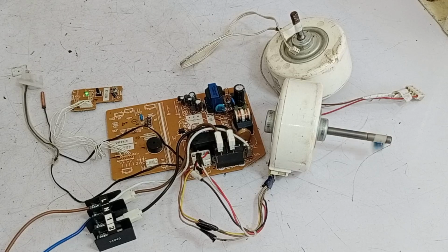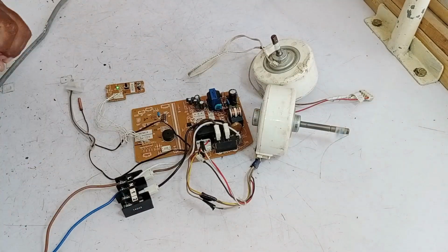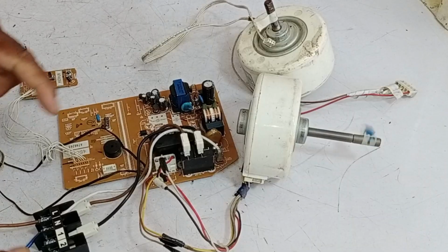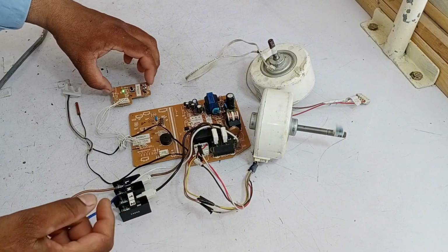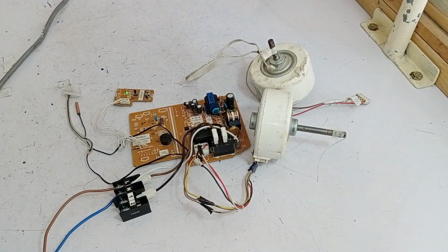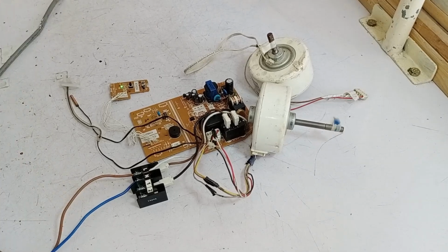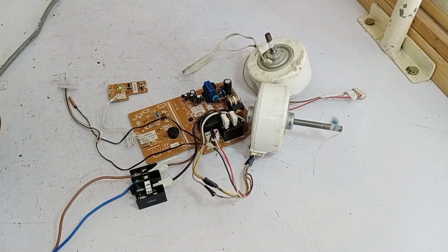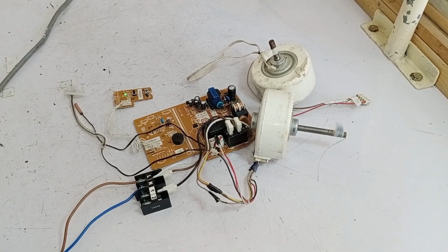Here, you can see that I've started the unit and the green light has turned on. The motor has also started running. I've set up two motors here. This motor is compatible with the unit, and since it's compatible, the unit's power supply and other outputs are functioning correctly without causing any tripping. You can see that the indicator light is on, showing that the output is active. Now, I'll connect the other motor and I'll demonstrate how it causes tripping. This will help you understand how using an incompatible or faulty motor can lead to tripping issues.